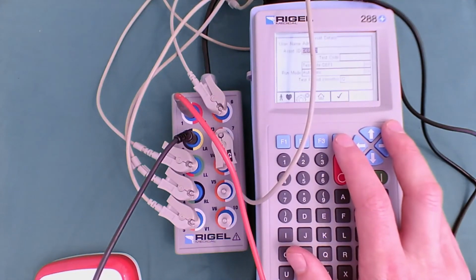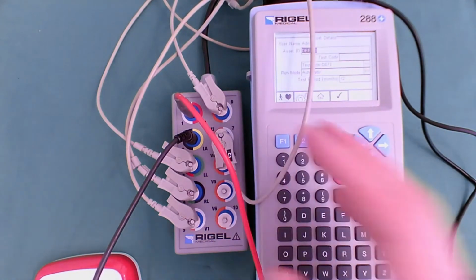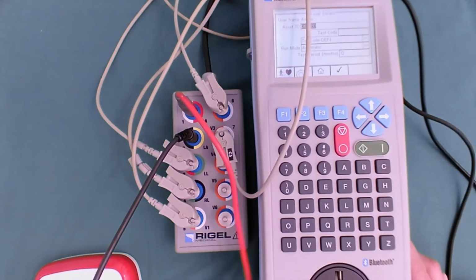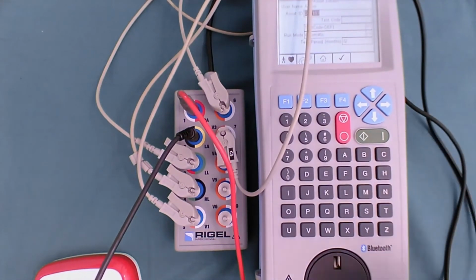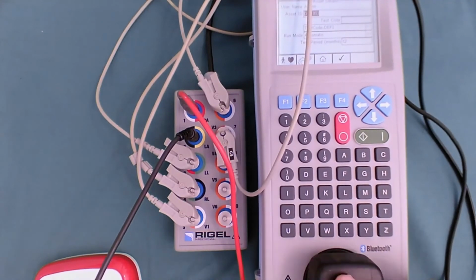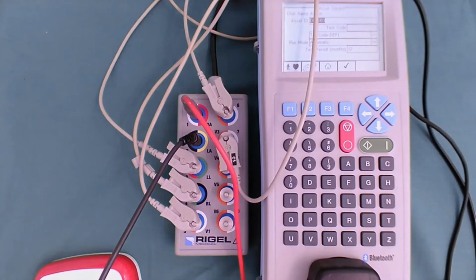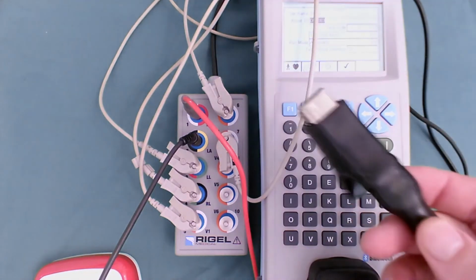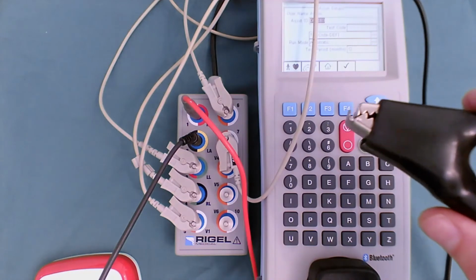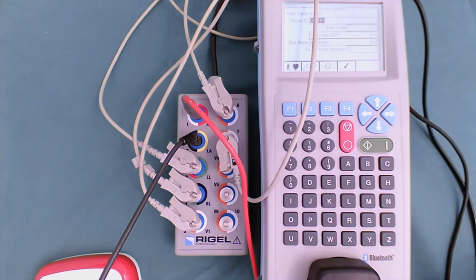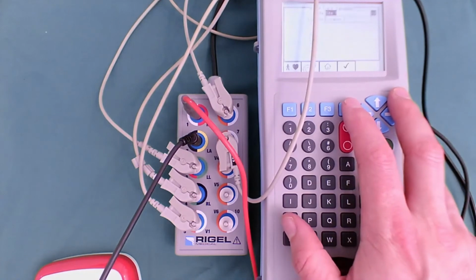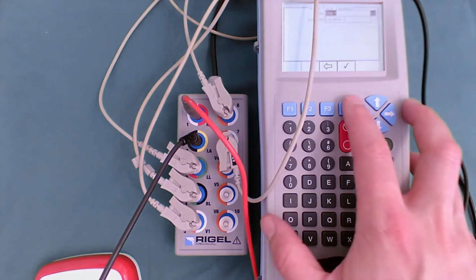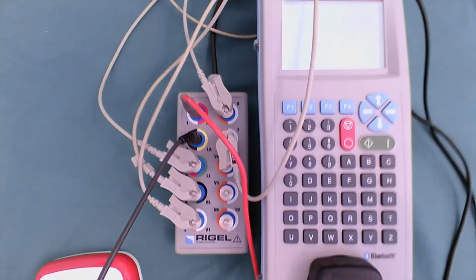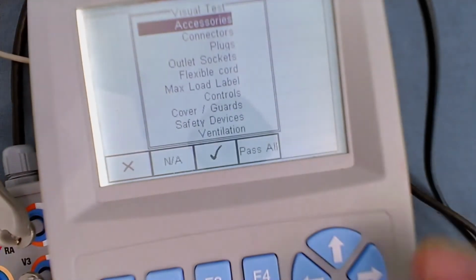So then if you want to recall this DEFI test code, it's already pre-configured for any defibs you're going to be using with 5 ECG leads. And then same as before, plug the device under test into the DUT socket, connect up your enclosure type lead to any exposed conductive parts on the enclosure of the equipment under test, and then perform an automatic or semi-automatic test as before. And the 288 will take care of the rest. It will work out all the values, we can see that with the visual test from our pre-configured test sequences there.